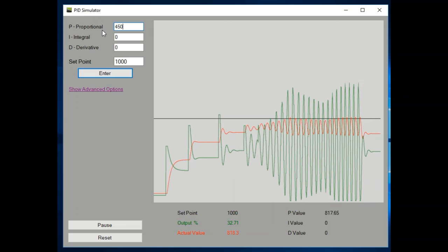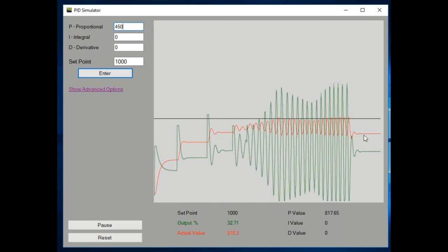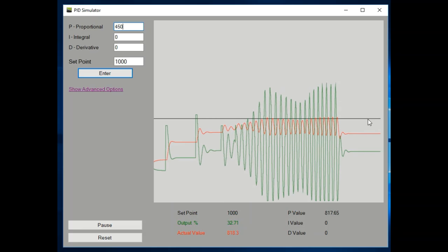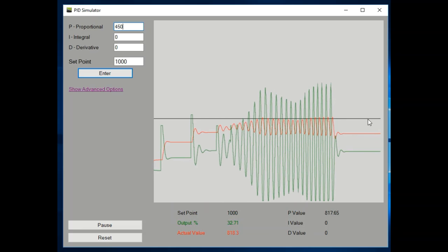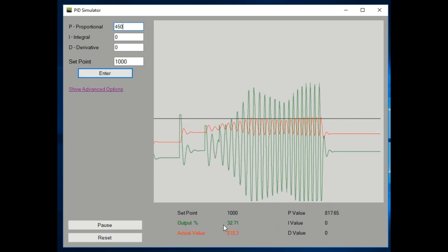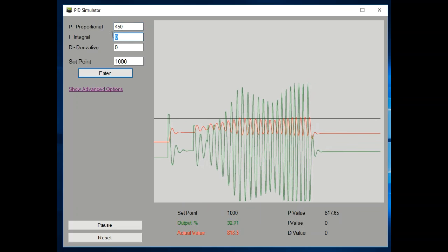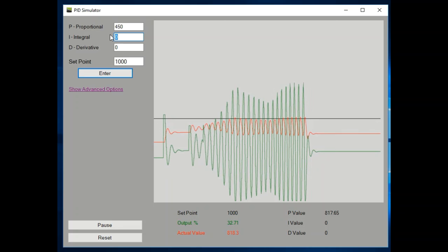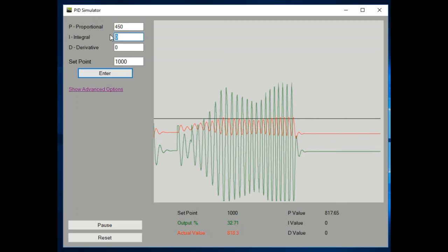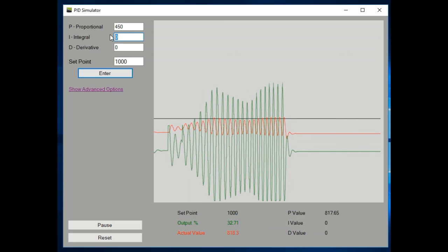After we have the proportional, notice how the actual value hasn't reached the set point yet. With the output being only at 32, the actual value hasn't reached the set point. That's common with a proportional value. To get the actual value there, we need the integral. The integral is going to increase that output over time, accumulative, to bring the actual value to the set point.